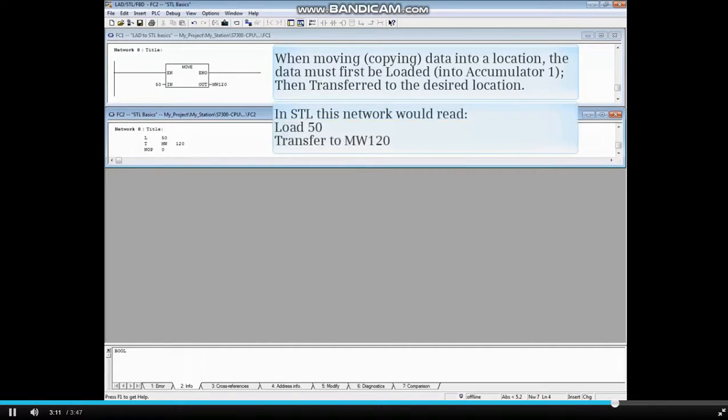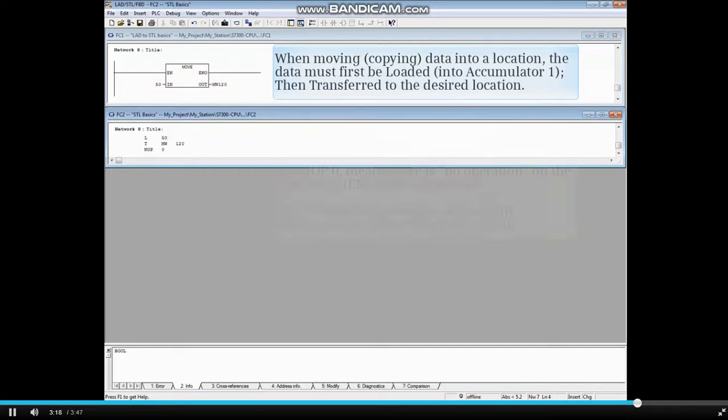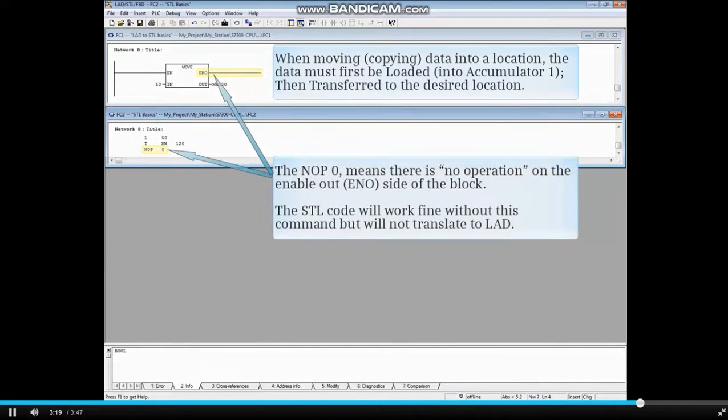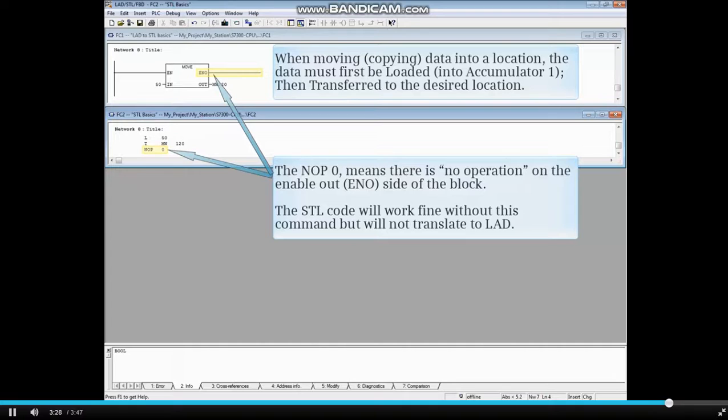In STL, this network would read: load 50, transfer to memory word 120. The NOP 0 means there is no operation on the enable out or ENO side of the block. The STL code will work fine without this command, but will not translate to LAD.